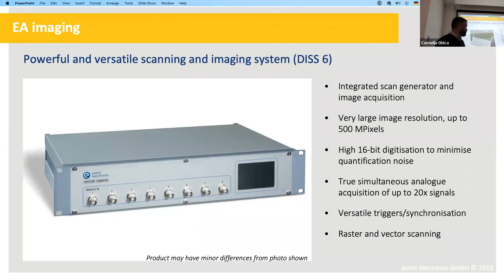And it's also very important that we need to acquire two signals simultaneously. So that means move the beam, stop the beam, get all the signals you want, and then move the beam again, as a way of ensuring that when you overlay the images, they overlay exactly, so your field is not somehow shown in a different part of where it should be.